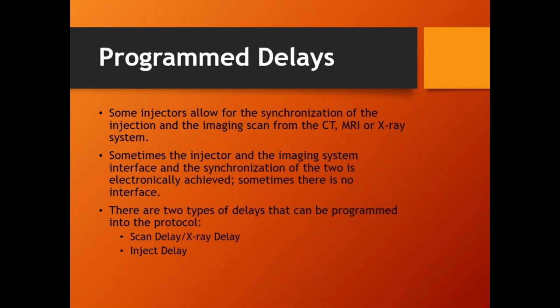Delays. Now there's 2 kinds of delays, but they go by 3 different names. It'll make sense. There is a scan delay and an X-ray delay, which are the same thing, and then there's inject delay. So let's start off with inject delay. It's the easiest. Remember, when we're doing the injection with the contrast injector, we're also firing X-rays into the patient. So I have to hit the X-ray exposure switch, and I have to hit the injector start switch. Let's just leave that aside for right now and just know that both of these things are happening at the same time.